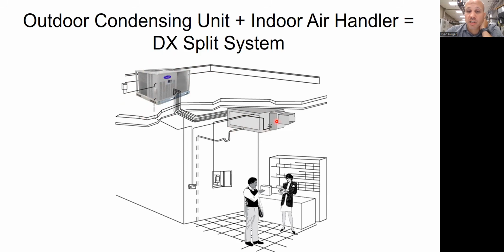We have to be a little bit smart on where you locate the indoor unit. Like in this case, it's in the ceiling. There is going to be a condensate pan and there is going to be a condensate drain, just like your system at home has, but now it's above the ceiling. So it's important to know what's going to be located underneath it. Do I want to do this in a server room with a bunch of expensive servers? No, I don't want water above electrical servers. Pass. That's a hard no, right?